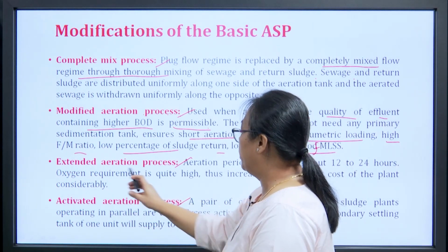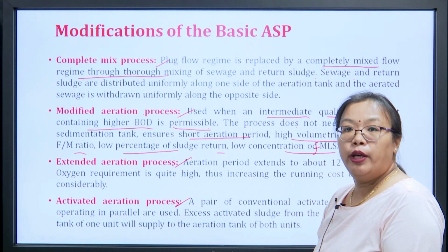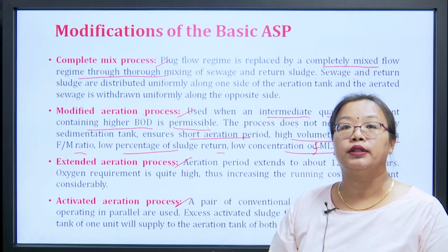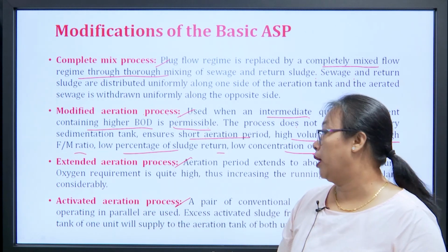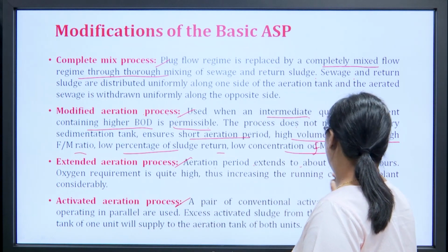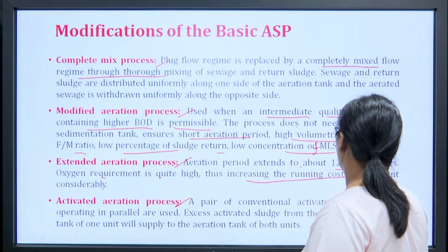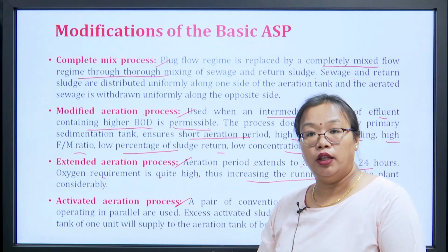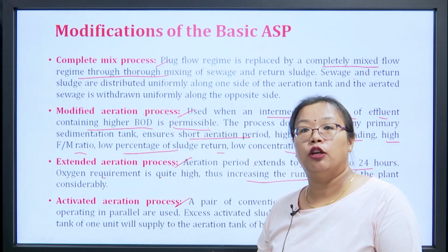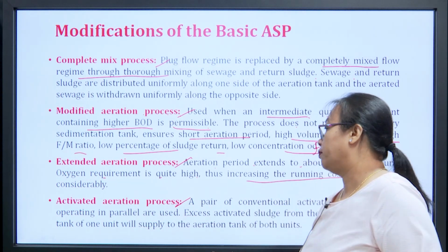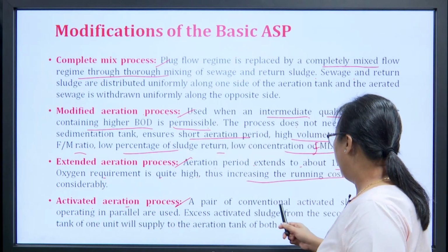Another is the extended aeration process. Extended aeration में क्या है, आपको नाम से ही पता चल जाएगा. Here we are going to go for extended aeration. Aeration आपको ज़्यादा देर के लिए देना है, मतलब you are going to aerate the wastewater for a longer period of time. So the aeration period extends up to 12 to 24 hours. Oxygen requirement is quite high, thus increasing the running cost of the plant. तो अगर आप ज़्यादा oxygen लेंगे और ज़्यादा देर pump चलाएंगे तो obviously electricity ज़्यादा consume होगा, तो obviously आपका operating cost ज़्यादा हो जाएगा.